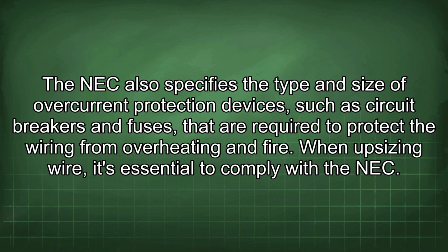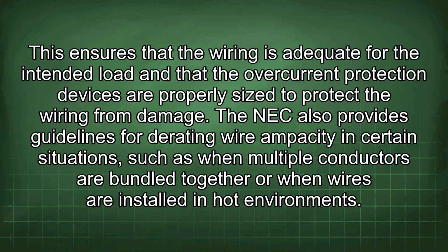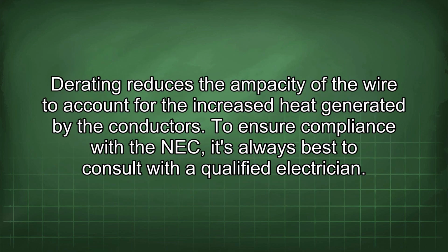When upsizing wire, it's essential to comply with the NEC. This ensures that the wiring is adequate for the intended load and that the overcurrent protection devices are properly sized to protect the wiring from damage. The NEC also provides guidelines for derating wire ampacity in certain situations, such as when multiple conductors are bundled together or when wires are installed in hot environments. Derating reduces the ampacity of the wire to account for the increased heat generated by the conductors.